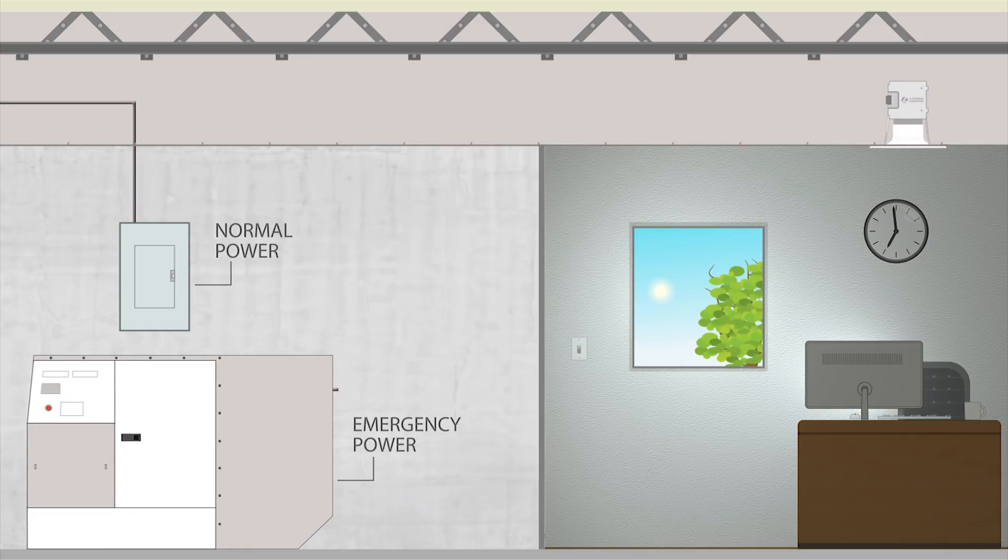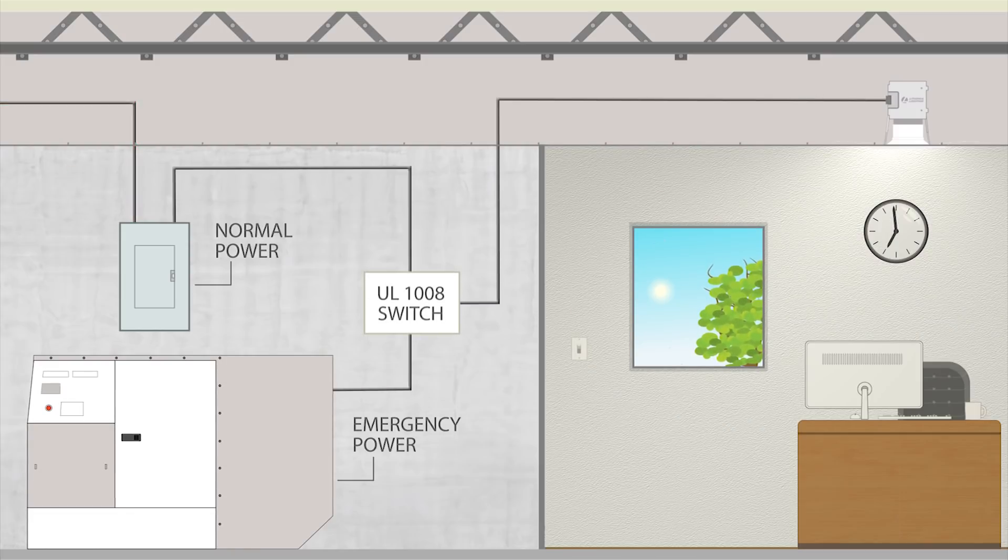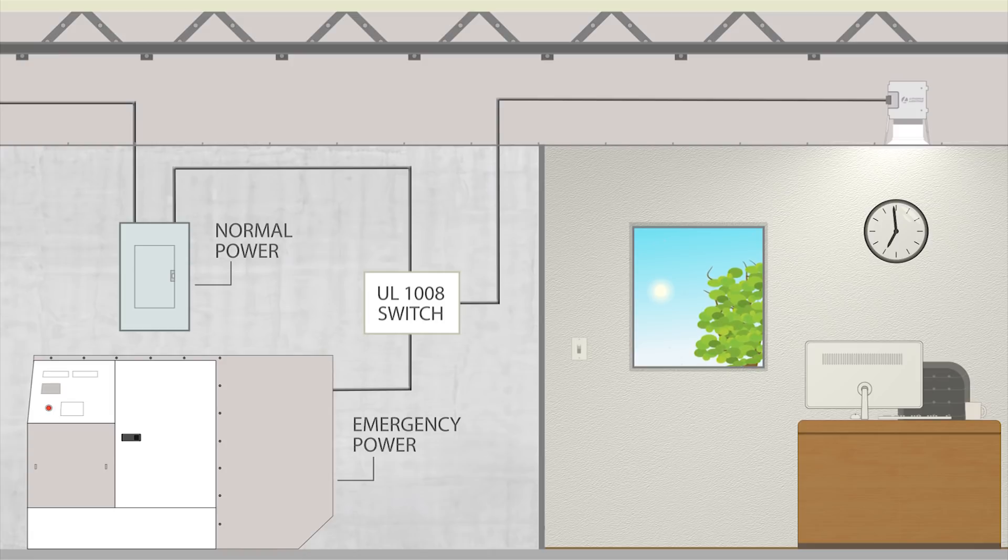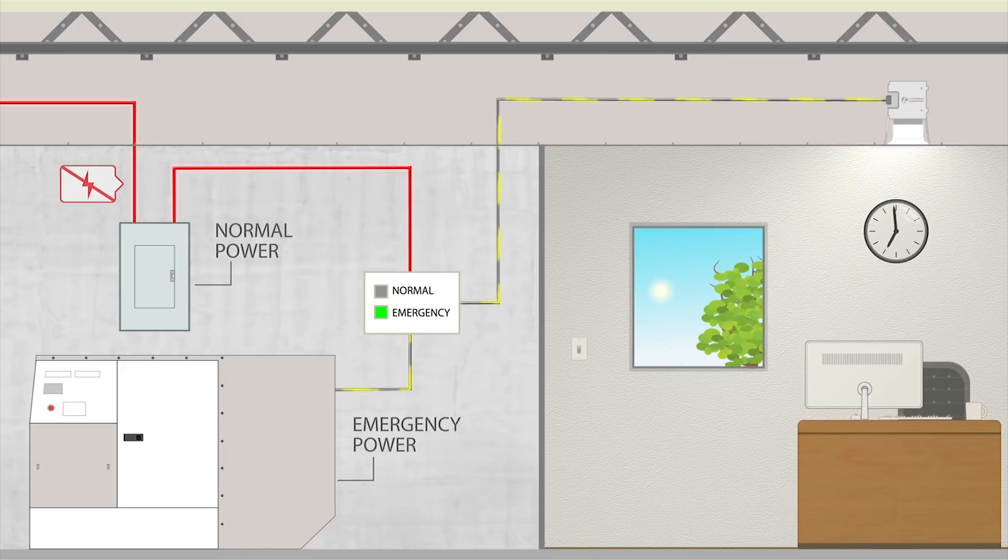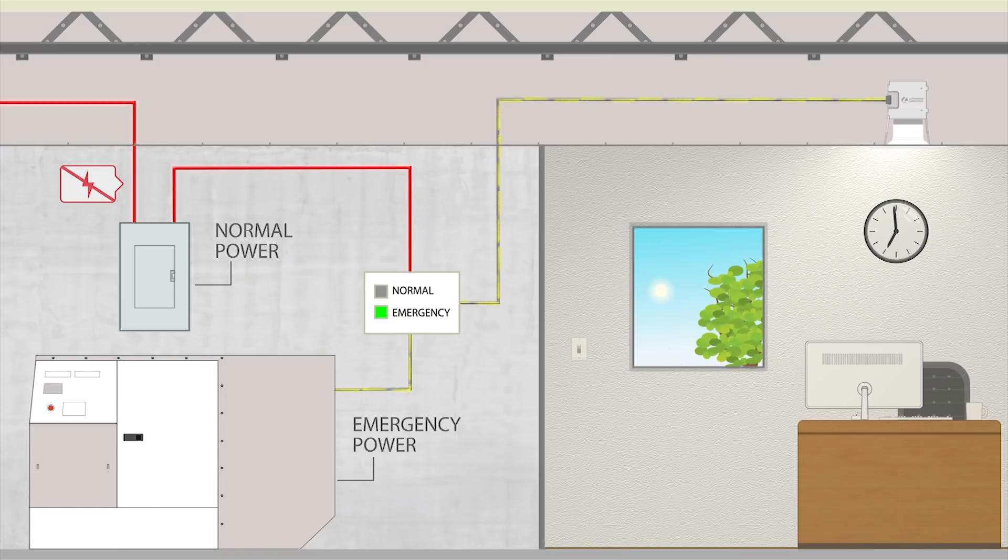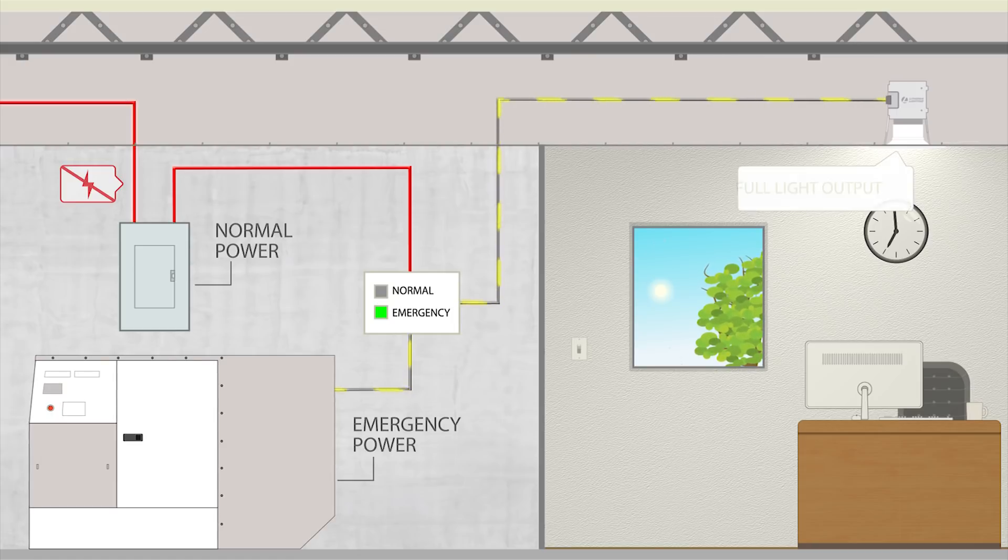Controlling this transition from normal to auxiliary power is a UL-1008 switch device, which activates when normal power is lost, and allows the luminaires to receive power from the auxiliary supply. This common application provides a simple solution for emergency backup power that delivers full light output for the required duration.